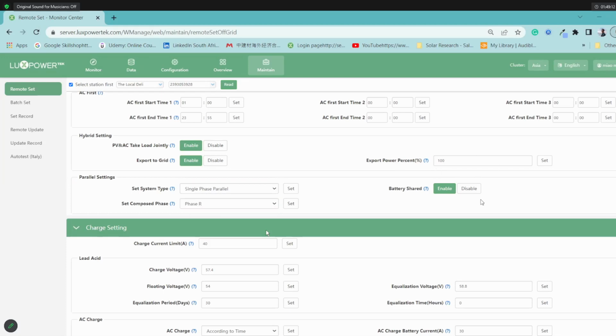Battery shared, as previously stated, please make sure this is enabled, parallel your batteries, and use a bus bar to then connect it to all of the inverters in the parallel connection. This is recommended.